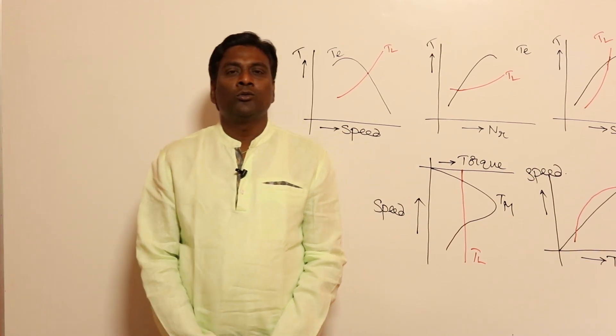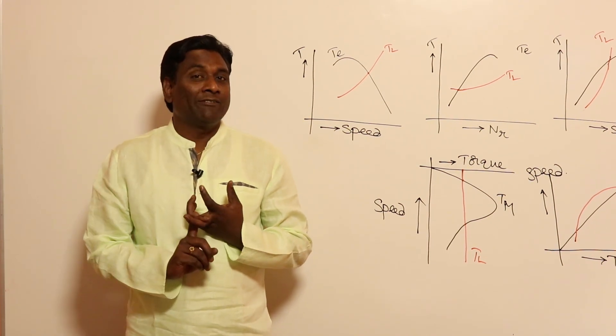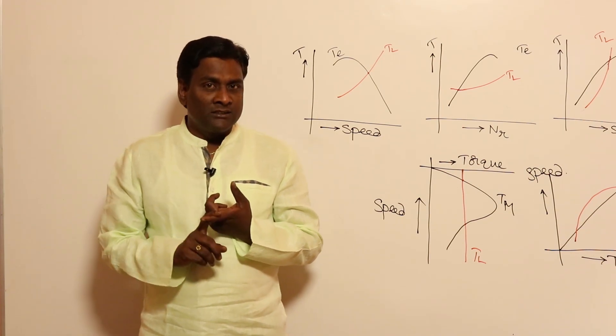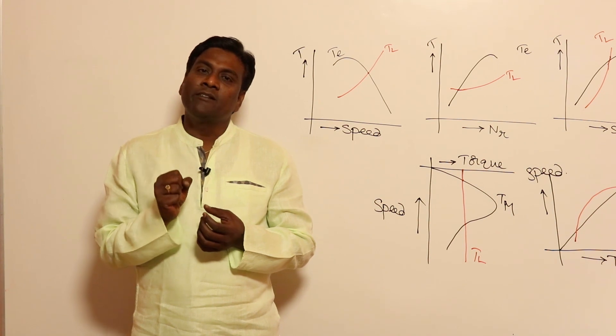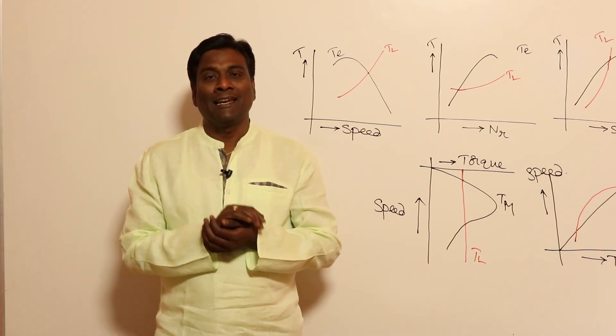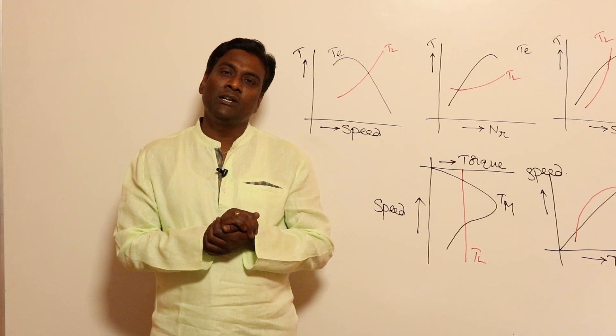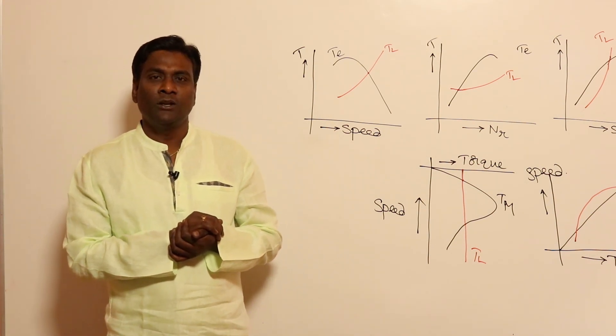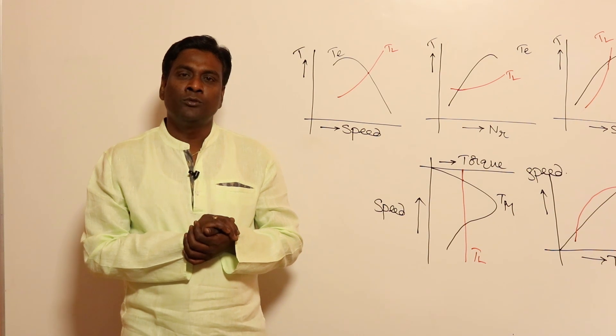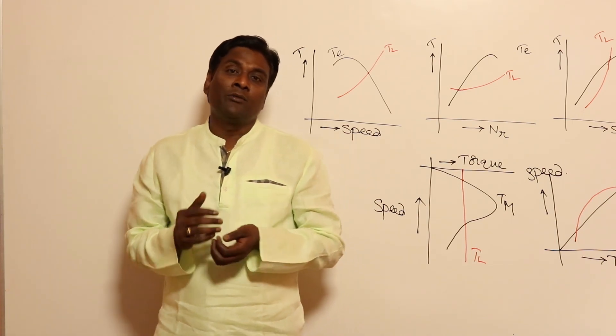In this session, let us see how to calculate stable operating point. The torque developed by the motor will have a characteristic, and the torque requirement of the load will also have a characteristic. For constant load torque in an induction motor, the torque requirement may not always be constant in practice. For example, in metal cutting (solid to solid), torque requirement is constant; in solid to liquid, it is proportional to speed; and in solid to air, like ceiling fans, torque is proportional to speed squared.